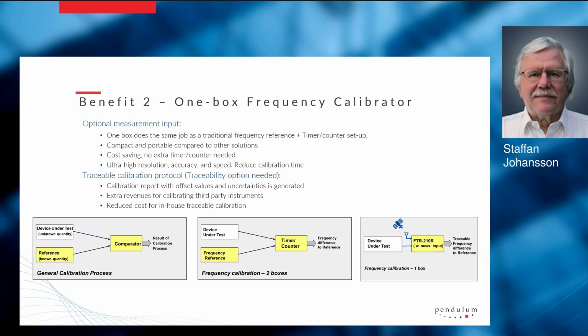And let's have a look at the graph on the bottom. The general calibration process is a comparison between a reference, a known quantity, and a device under test with an unknown quantity. The result of that comparison is the data plus stated uncertainty. The reference used should be traceable to an international or at least a national standard. That is the general calibration process for any type of parameter that you want to calibrate.